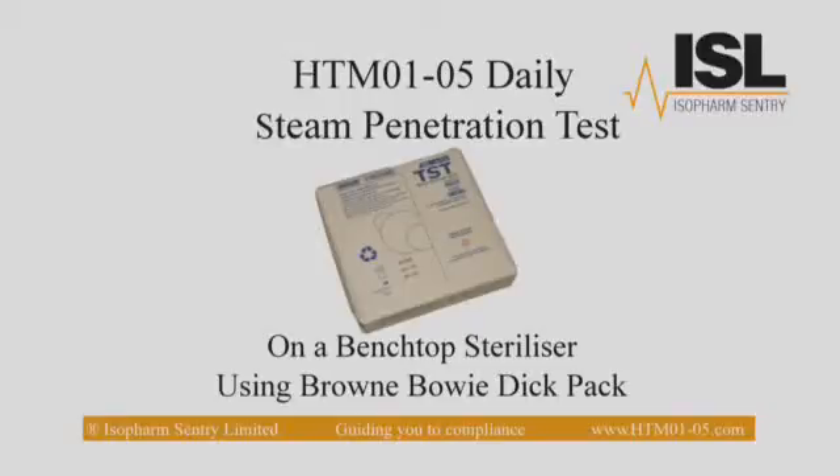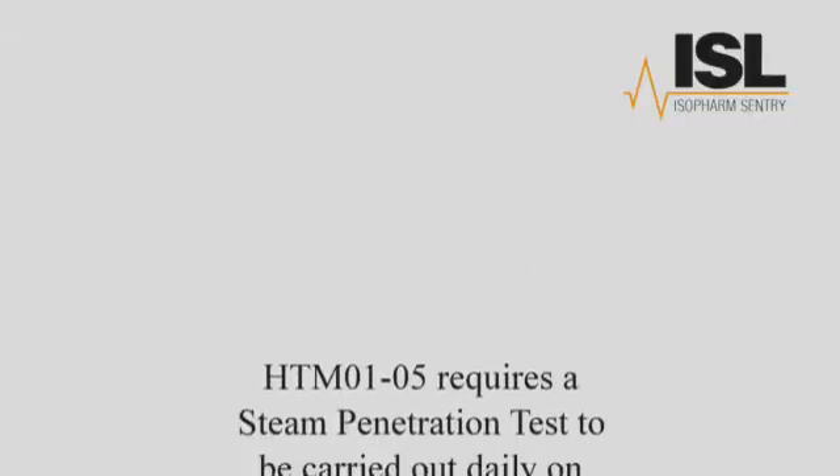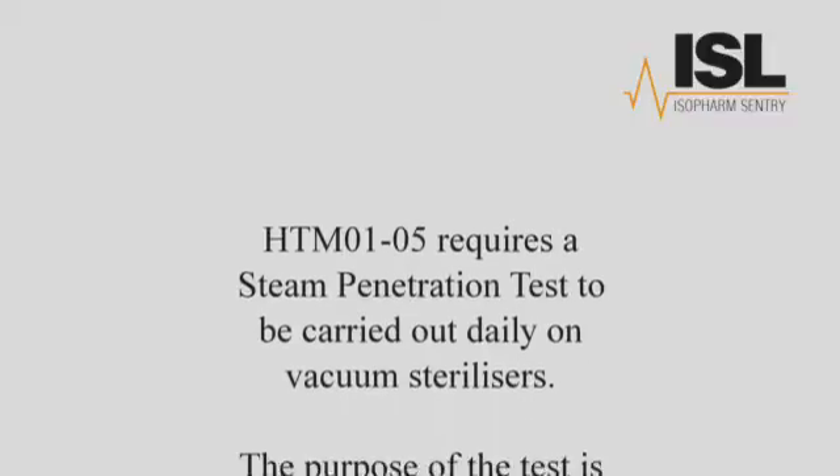HTM01-05 Daily Steam Penetration Test on a benchtop steriliser using Browne Bowie Dick Pack. HTM01-05 requires a steam penetration test to be carried out daily on vacuum sterilisers.